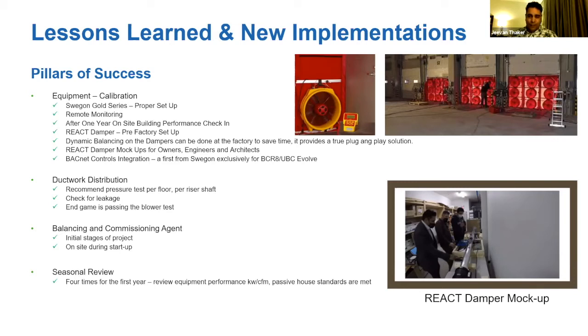So good and bad. We had some issues. We went to the attic space and found 7 gaping holes in the ductwork. We patched those up, and all of a sudden, at the end of our main duct, we had the full CFM that we needed to achieve, right? So small things like that. And again, it's hard to believe, but it happens all the time. Again, 30 projects, quite a few of them, we've talked about that.